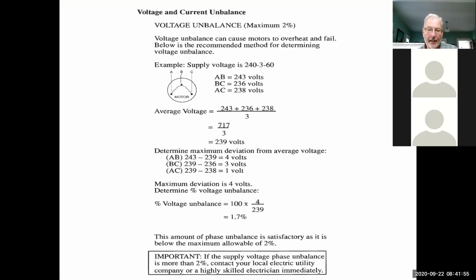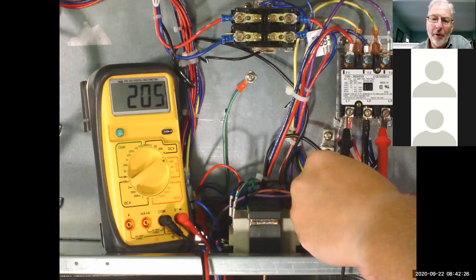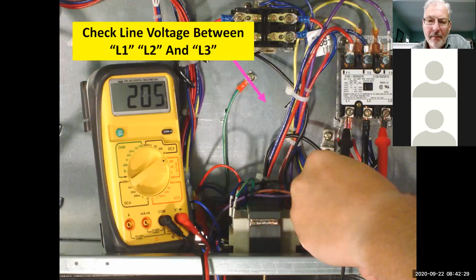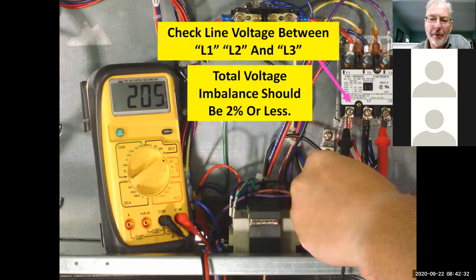Okay, so if you look at this, and I don't have the sheet up here, but this is how we do it. We check A to B, B to C, and then A to C. Check our voltage, add them up, divide them by 3 for our average voltage, and then take our deviation to the farthest voltage, and that's our percent of imbalance. In this case, it's 1.7. I got a couple examples here that we're going to talk about. So in other words, go A to B, or line 1 to line 2, line 2 to 3, line 1 to 3. Make sure we're 2% or less.